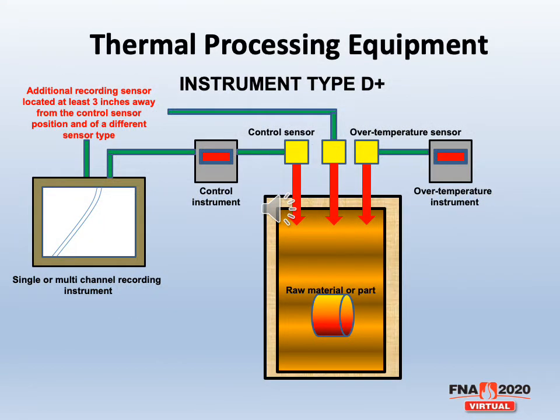There now is a new instrumentation type in AMS 2750F. We now have instrument type D+. Prior to this, we had instrumentations A through E in Rev E, and now we have D+. So D+ instrumentation is an additional recording sensor that is located at least 3 inches away from the controlling sensor position, and it also has to be of a different type sensor.